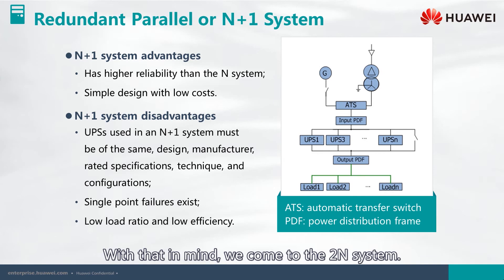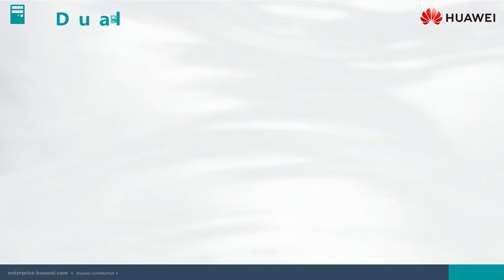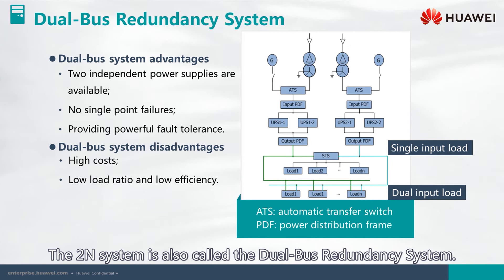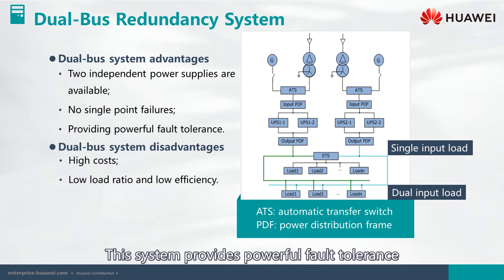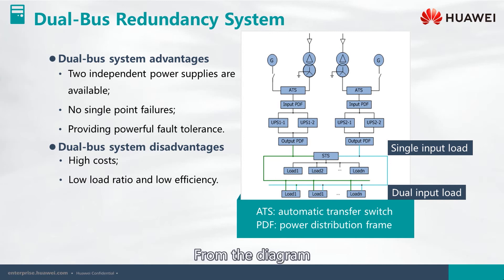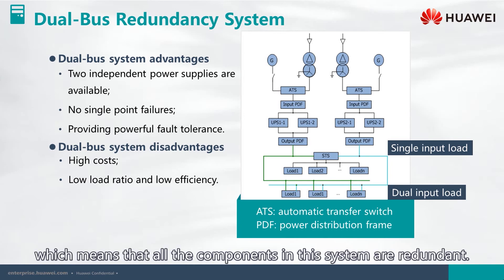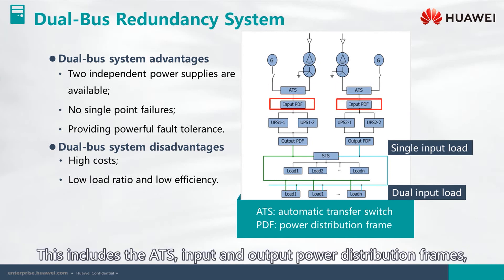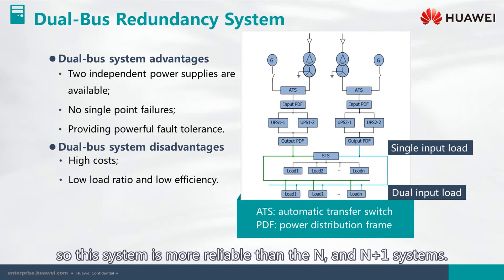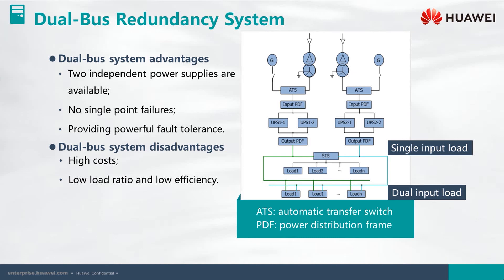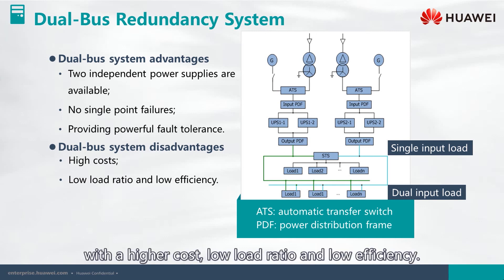With that in mind, we come to the 2N system, also called the dual bus redundancy system. This system provides powerful fault tolerance and there are no single points of failure. From the diagram, we can see that there are two independent power supplies. All the components in this system are redundant, including the ATS and input and output power distribution frames. So this system is more reliable than the N and N plus one systems. However, this comes at a high price, with higher cost, low load ratio, and low efficiency.